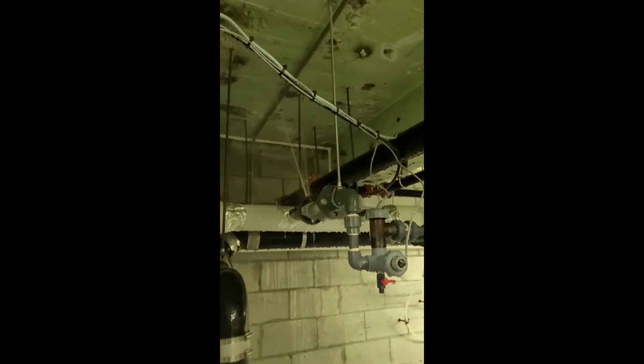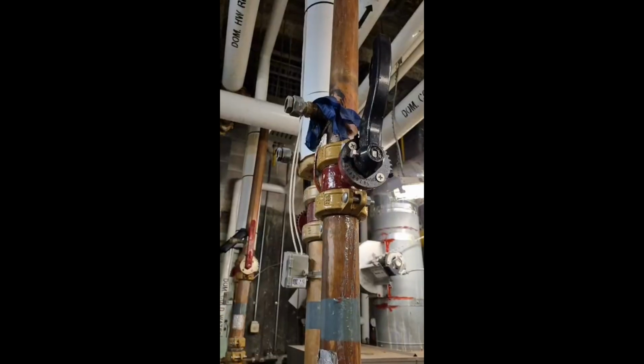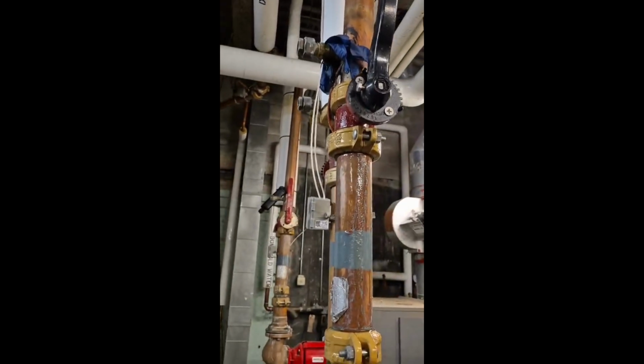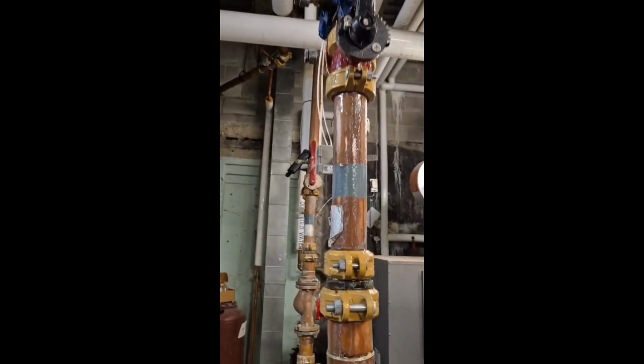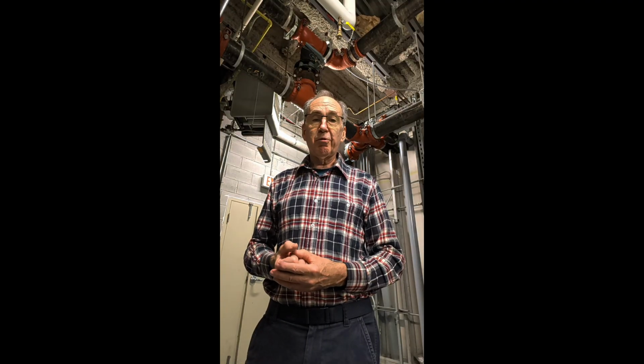Our mechanical rooms get checked once a day, six days a week by staff. But if a pipe bursts or something breaks and water starts flooding onto the floor, it could be hours before anyone notices, and if it happens on a Saturday afternoon, it could be a day and a half. Having a way to know immediately that there's water on the floor lets us mitigate the issue right away. It often makes the difference between a relatively small cleanup and tens, or even hundreds of thousands of dollars worth of damage.